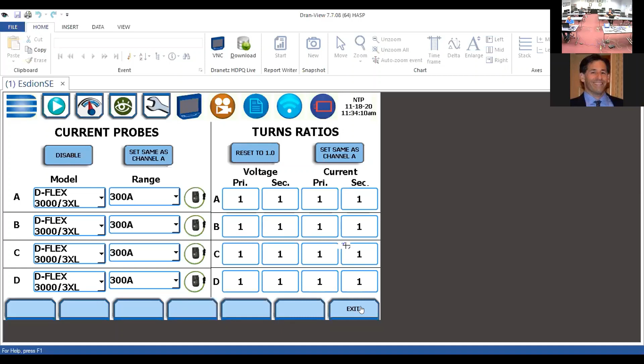This screen allows you to do some sanity checks, making sure the amperage is what I expect it to be. In some cases, you might be making a connection before the circuit is energized, so that's an exception, but most of the time you're going to be connected with some semblance of current. So you want to make sure it's reading the correct voltage values, and roughly the correct current values.